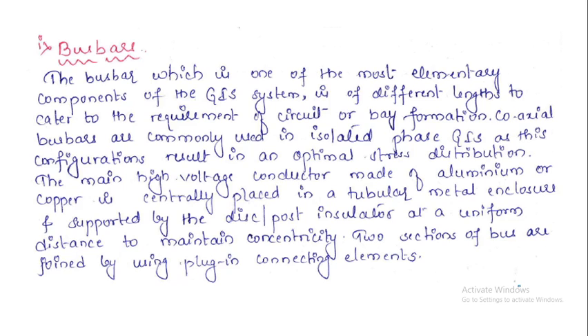The bus bar, which is one of the most elementary components of the GIS system, is of different lengths to cater to the requirement of a circuit or bay formation. Coaxial bus bars are commonly used in an isolated phase GIS, as this configuration results in an optimal stress distribution. So coaxial bus bars will be commonly used in gas insulated substations.